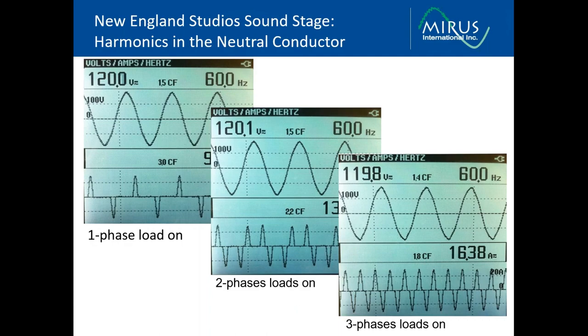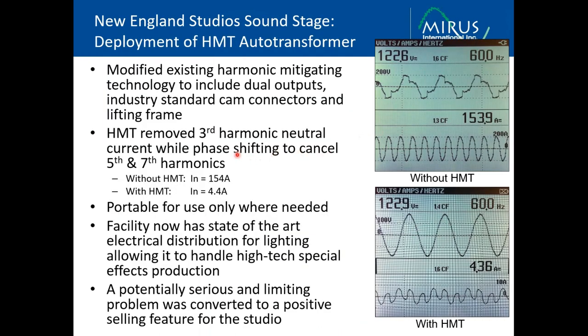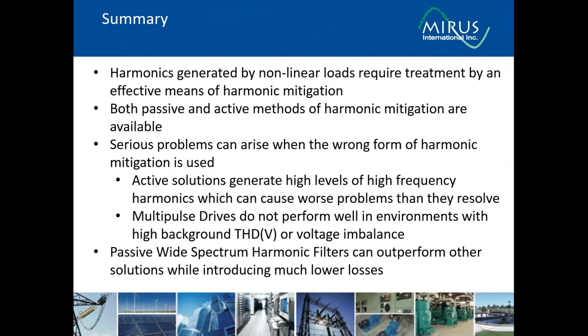So we introduced the passive solutions and dropped the neutral current from 154 amps to 4.4 amps. You can see the current measured here: 154 amps, predominantly third harmonic. Here's your scale at 200 amps. With the filter installed, the scale is 10 amps now, at 4.3 amps. So a dramatic reduction. We can deal with single-phase harmonics with passive solutions just as well as we can the three-phase harmonics introduced by variable speed drives.